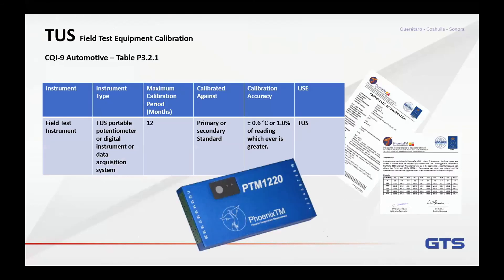The actual device you're using for your survey has strict calibration requirements under CQI-9. You need to calibrate the logger at a minimum of every 12 months — more frequently is obviously recommended as it gives you more confidence. The calibration accuracy for the device has to be plus or minus 0.6 degrees Celsius or 1% of the reading, whichever is the greater value.